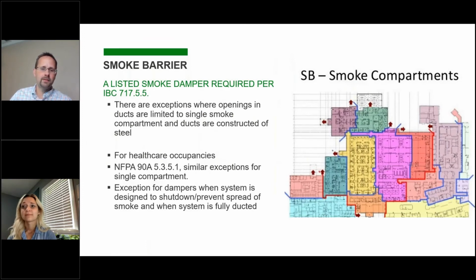Yeah, so smoke barriers in general, a smoke damper is required when you penetrate a smoke barrier, but there are exceptions. One thing I want to say about that, though, is as Glynis mentioned, it's required to have a 1-hour fire resistive construction, but that doesn't mean it needs to be a fire smoke damper. That is a common misconception, and you don't necessarily have to put a fire smoke damper just because it is a smoke barrier and it's required to be done that way. Sometimes you'll see on a code plan someone has put 1-hour fire smoke barrier just because it's required to have that construction type, and that can throw you off.